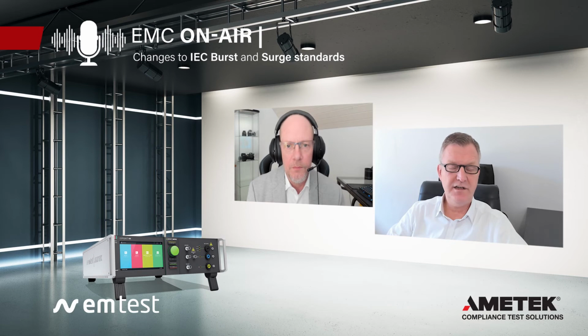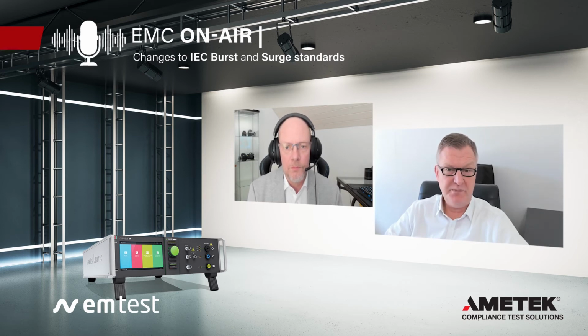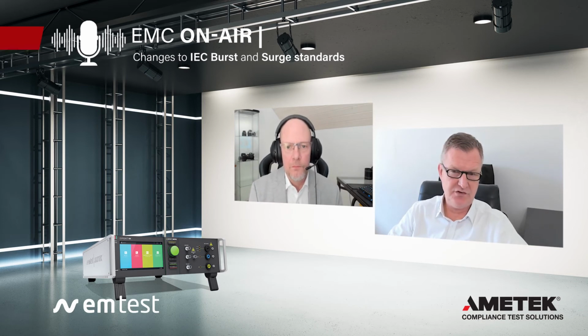Yeah. So in the previous standard, we had the specification of 5 kilohertz for the so-called spike frequency. This is a pulse. The pulse is in the burst package, because burst pulses always come in a package. And this was changed to 5 or 100 kilohertz. So if you select 100 kilohertz, which is closer to reality, you need to minimize the width of the burst package so the energy isn't changed. So we always use 75 pulses in a package.